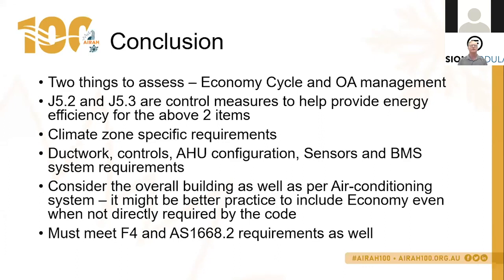Then you've got a period where you can modulate chill water valves and heating water valves and still run mostly economy mode, where you'll just do a minimal amount of cooling or heating. And so that's quite effective from an energy perspective. And then, of course, you jump up the psychrometric chart to the point where you've got full control via the chill water system or the heating water system. Same with the DX system, if you've got that capability in your DX plant.